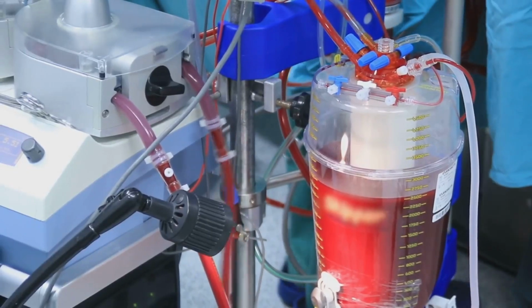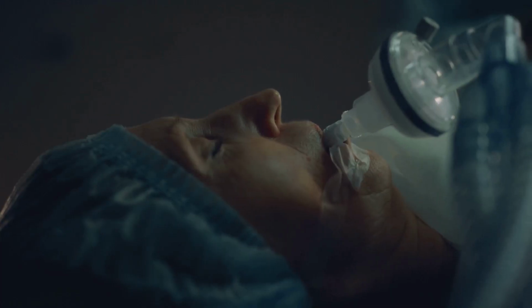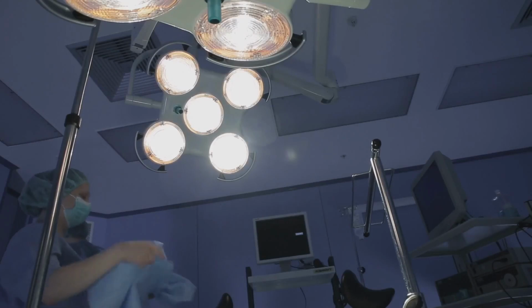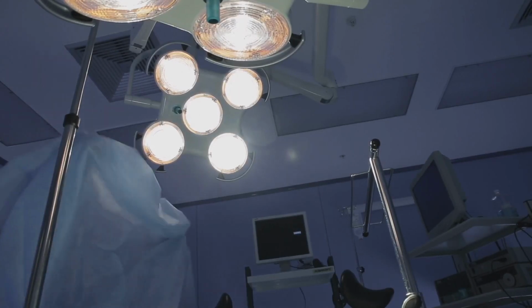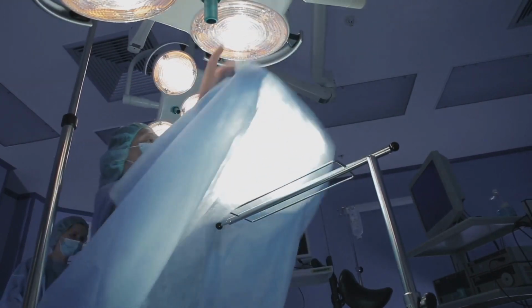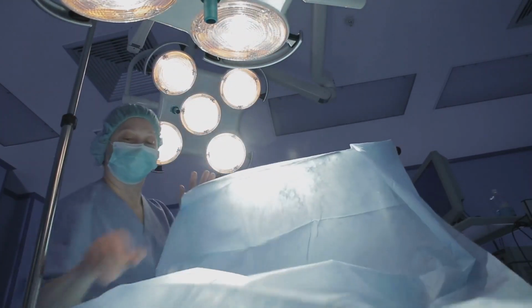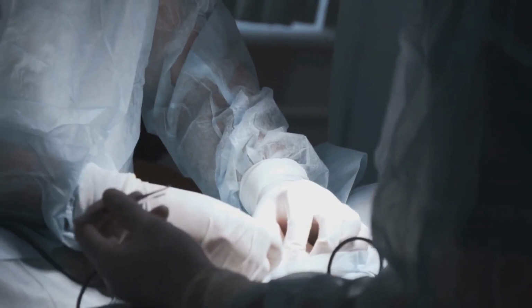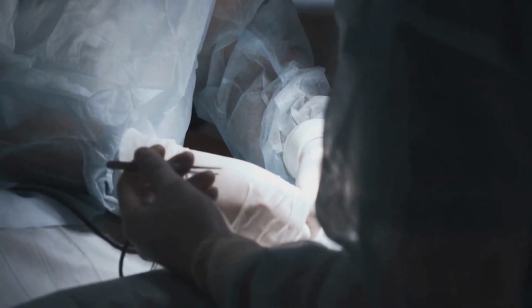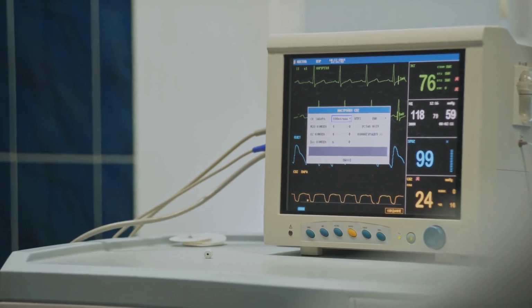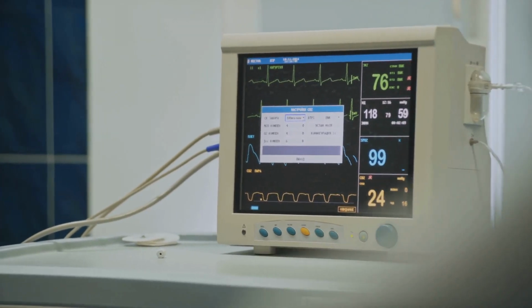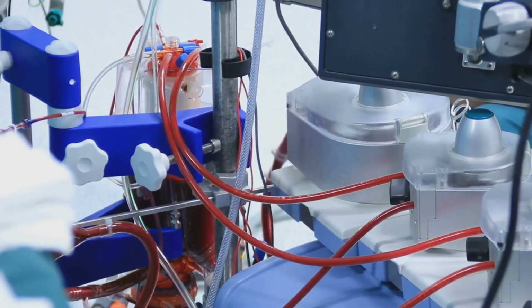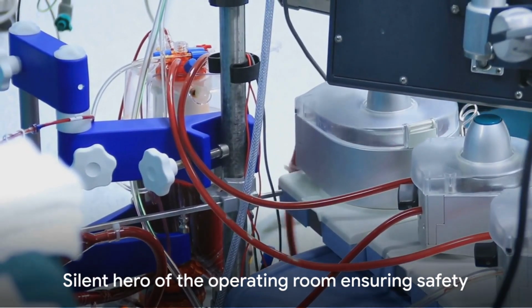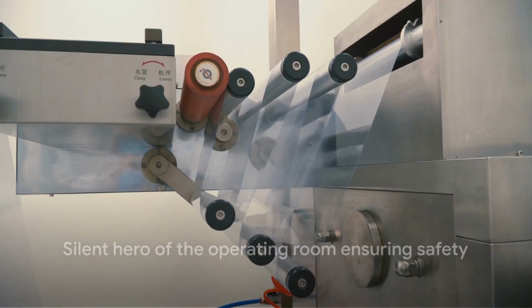The anesthetic gas scavenging system is not just about maintaining a clean air environment, though. It also plays a role in controlling the pressure within the patient's breathing circuit. By removing excess gases, it helps prevent the buildup of pressure that could potentially cause harm to the patient. This system is a testament to the intricate design and thoughtfulness that goes into the construction of an anesthesia machine. Every component, every mechanism, is there for a reason, playing its part in ensuring the safety and efficacy of the anesthesia process. In essence, the anesthetic gas scavenging system is a silent hero of the operating room, tirelessly working to ensure a safe environment for both the patient and the healthcare team.